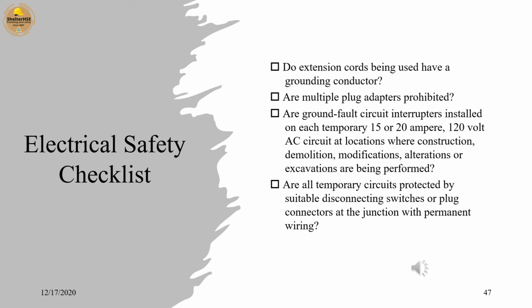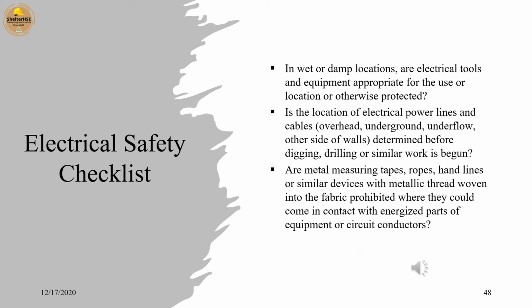Are all temporary circuits protected by suitable disconnecting switches or plug connectors at the junction with permanent wiring? In wet or damp locations, are electrical tools and equipment appropriate for the use or location or otherwise protected? Is the location of electrical power lines and cables, overhead, underground, underfloor, other side of walls, determined before digging, drilling or similar work is begun? Are metal measuring tapes, ropes, hand lines, or similar devices with metallic thread woven into the fabric prohibited where they could come in contact with energized parts of equipment or circuit conductors?